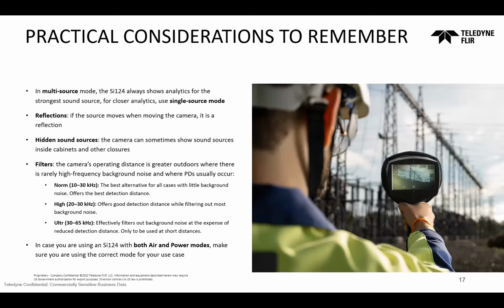The camera works with surface partial discharges. But in many cases, customers will ask you to try to find partial discharges inside cabinets, like electrical cabinets, and transformers. In both cases there isn't a 100% clear answer, but as a general reference, in cabinets the camera will often be able to find if there's a partial discharge without opening it, because sound can stick out through the slots in the joints of the doors, and the camera can detect it. So the camera will show sound coming from the door side, but that doesn't mean the partial discharge is located there - it means there's something inside that the camera is locating, and the sound is coming from there.